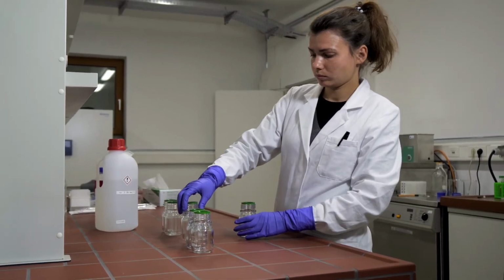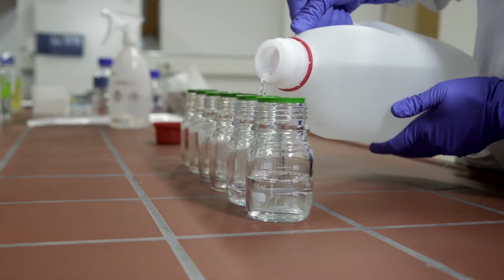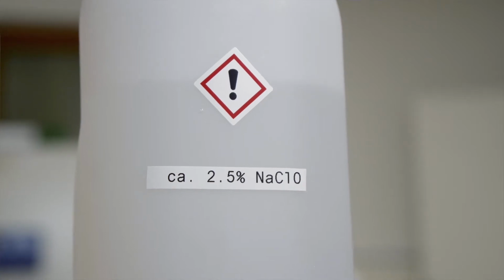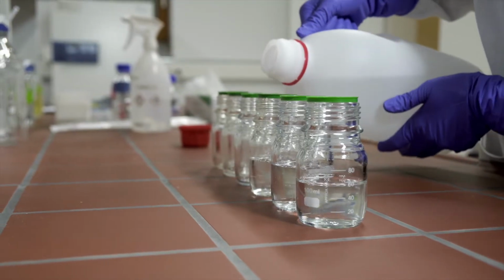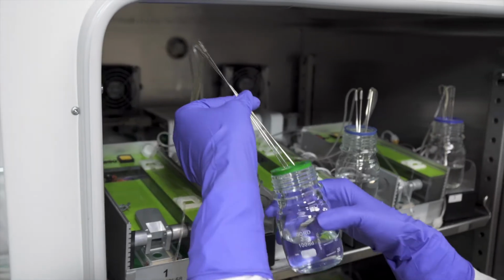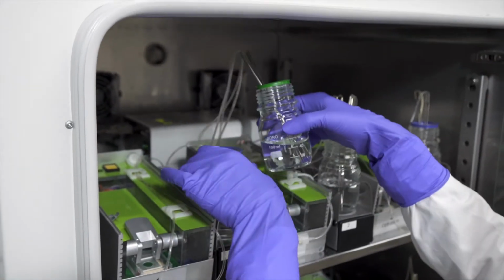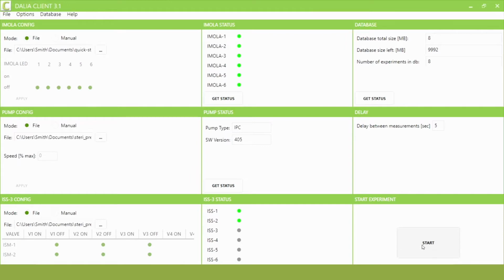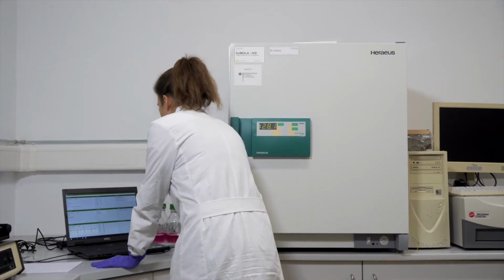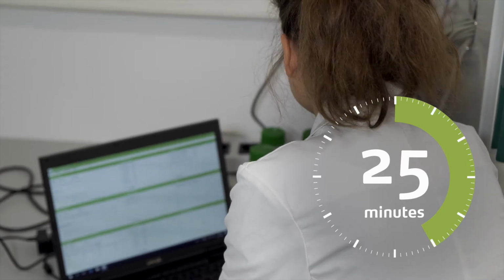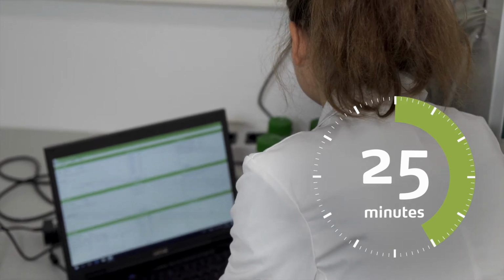To sterilize the whole system, add about 50 milliliters of 2.5% sodium hypochlorite solution to each of the 6 flasks and insert the 4 Luer steel connectors. If the software app Dahlia client has not been started yet, start the app on your computer. Choose the sterilization application and press Start. The sterilization process runs automatically for approximately 25 minutes.